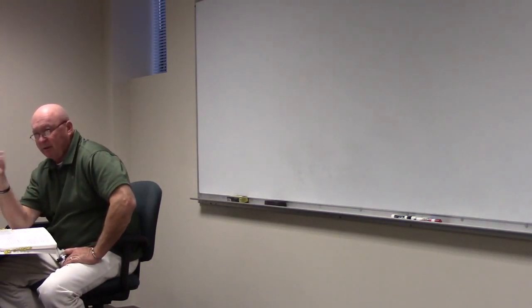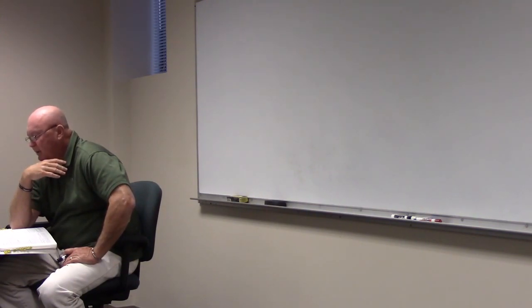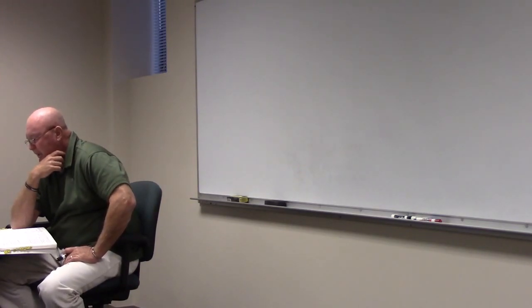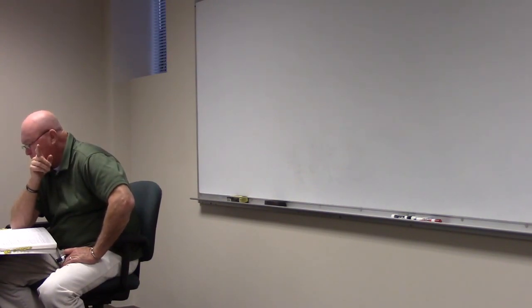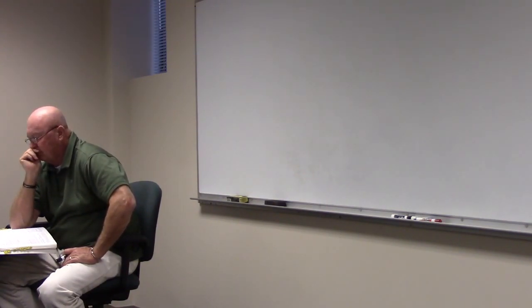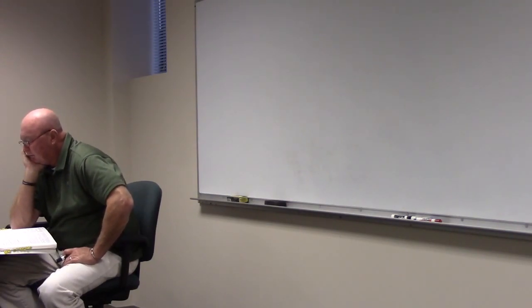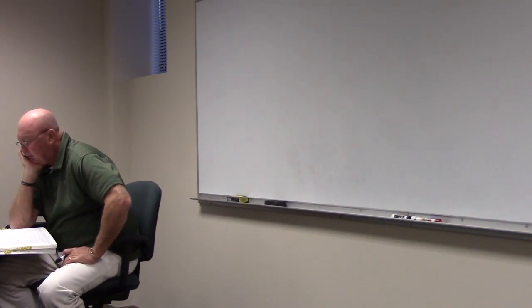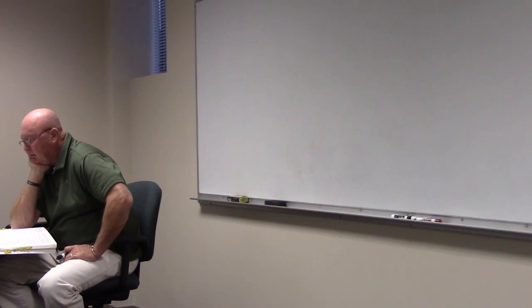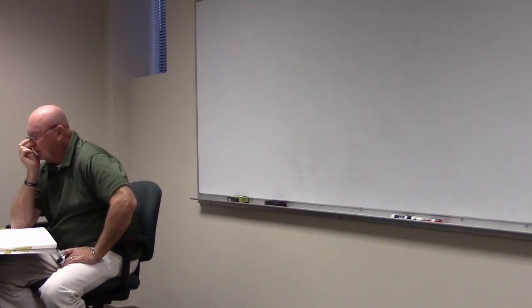Now, it's a little bit different than we learned in the other class, but let's kind of go through the steps. It's a step process. If you look at your floor plan there, you got a kitchen, 3 bedrooms, a living room, and a carport. Carport you need to remember. Look at the information it gives us. Concrete slab, no basement, unfinished attic, appliances: a 12 kW electric range, 4.5 kW water heater, washer, and a 5.5 dryer in the utility room. Gas heaters are installed in each room with no electrical requirements. What size service entrance would be provided for this residence if no other information is specified?